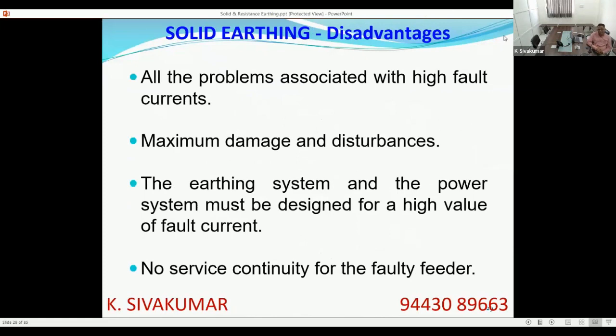Disadvantage: all the problems associated with high fault current. High fault current means thermal damage, the I squared T thermal damage. So all the touch voltages will increase. Whatever the high current related problems, they will always be there in a solidly earthed system, because the current is very high. And because the current is very high, damages are high and disturbances will be there.